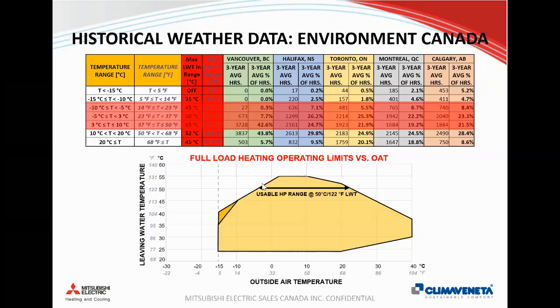So again, the operating envelope is kind of key for air-to-water heat pumps, and you need to understand the operating envelopes and the limitations of the technology, so that rather than design a system with a chiller and boiler and then say, okay, well, now what can I get out of the heat pump? The better approach would be to design the system around the heat pump capabilities. Maybe the heat pump doesn't need to supply 100% of the heat for all the systems in the building. Maybe there's some low-grade heat that you can use, depending on the application, to still have usable heat transfer into the building with supply temperatures.